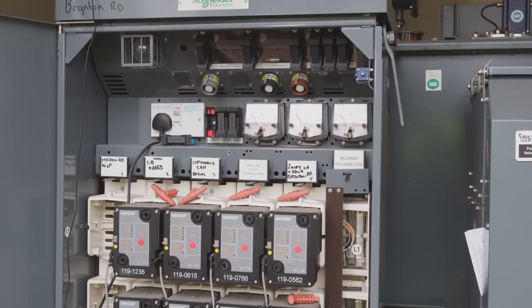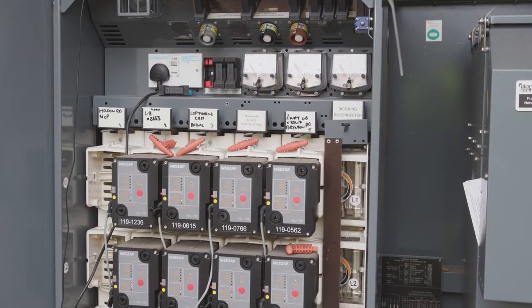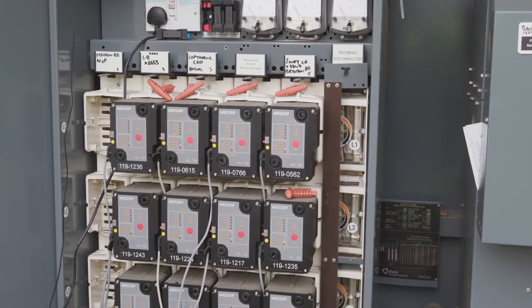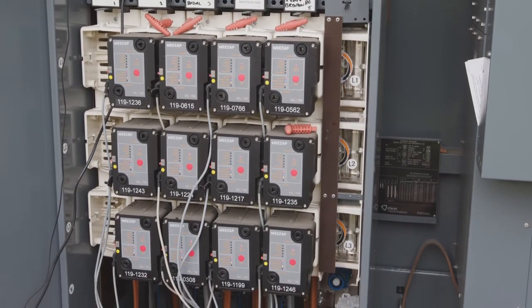We are also meshing the LV network together. At up to 720 LV ways, we will be replacing the standard fuse with an LV circuit breaker. Those circuit breakers will be remotely controlled and will provide measurement data from the substation, such as voltage and amps on the LV way.